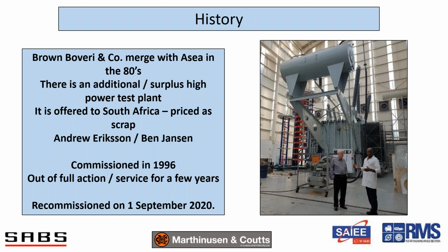So Ben was much younger at the time, and between them, the plant was offered to SABS, but they said no, they can't afford a plant like that, and the plant basically was offered as scrap and commissioned from that point. It was commissioned in 1996. It ran quite well. Then, due to maintenance issues, a couple of problems on the plant, it fell out of full action or full service for a few years. And as I mentioned in the beginning, we started work on it in late last year. We did the first current test on the 31st of August, and SABS kindly accepted the handover on the 1st of September.